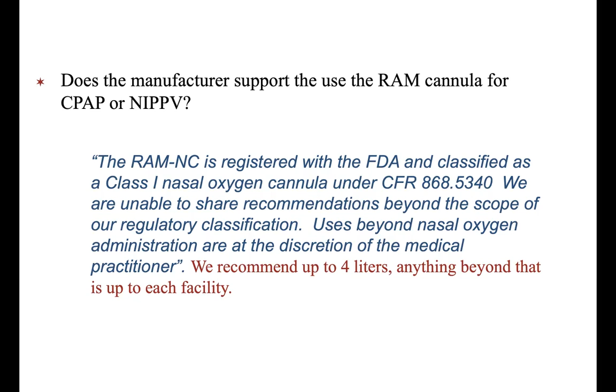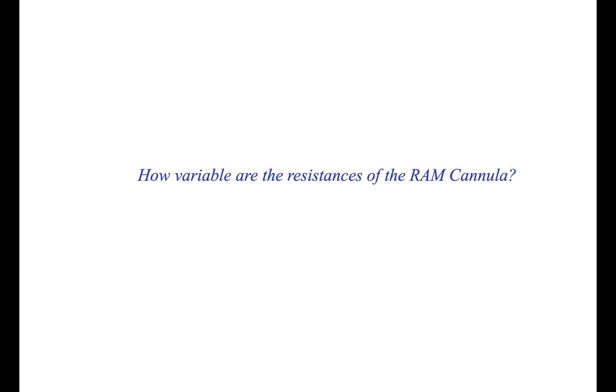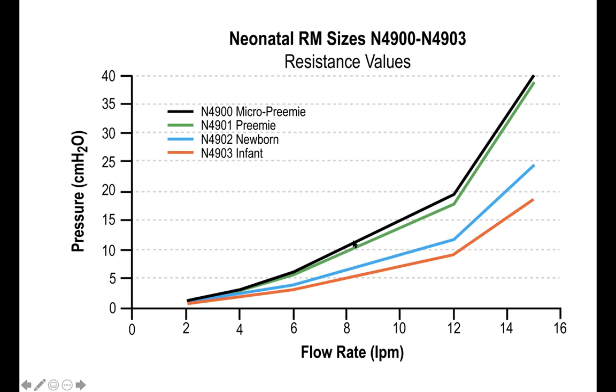We recommend up to 4 liters, which is not a very high flow rate for RAM cannula. Anything beyond that is up to each facility. One of the problems with the RAM cannula is that it has a very high resistance. And if you look here, again, this is manufacturer data from the 4 commercial RAM cannulas presently sold in the US, including micro, preemie, newborn, and infant. You can see here between 4 and 6 liters per minute in the micro, preemie, especially, the resistance of the RAM cannula goes up significantly.